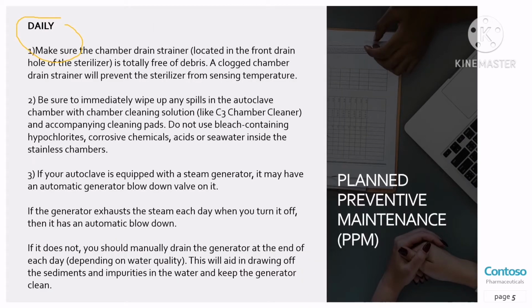Daily planned preventive maintenance for autoclave. First, make sure the chamber drain strainer located in the front drain hole of the sterilizer is totally free of debris. A clogged chamber drain strainer will prevent the sterilizer from sensing temperature. 2. Be sure to immediately wipe up any spill in the autoclave chamber with chamber cleaning solution and accompanying cleaning pads. Do not use bleach containing hypochlorite, corrosive chemical, acid, or seawater inside the stainless chambers.